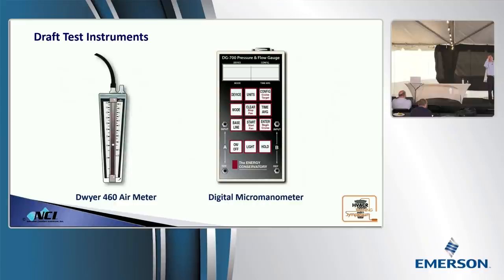Draft's going up. As draft goes up, combustion air does what? It increases. Because draft is the force that controls combustion air. So as draft goes up, combustion air increases. As draft goes down, what happens to combustion air? It decreases. It goes down. Uh-oh. Any movement down on that ball is a bad thing. Really bad. And you need to figure out why.